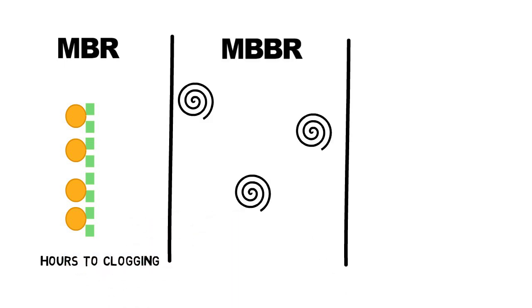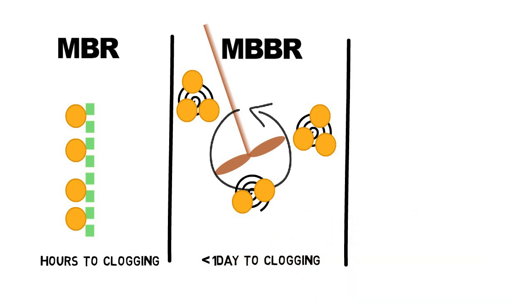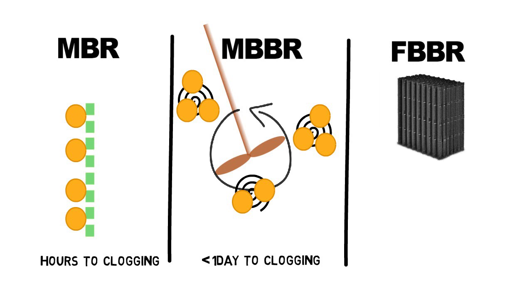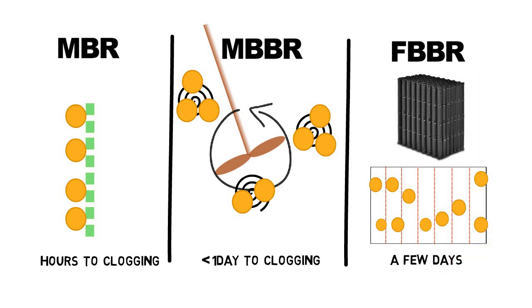MBBRs are less sensitive than MBRs although the risk of fill media clogging is high in case of interrupted mixing and grease leaks. Instead FBBRs are very robust and show very good handling of either changing influent values, grease leaks and interrupted oxygen supply.